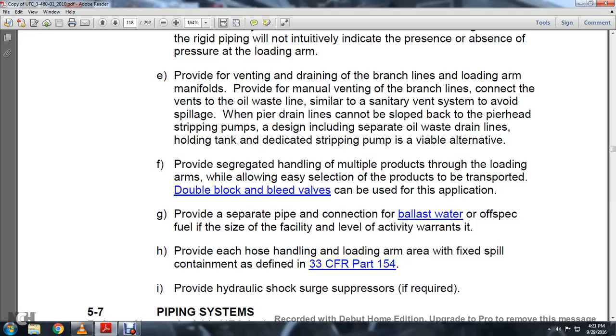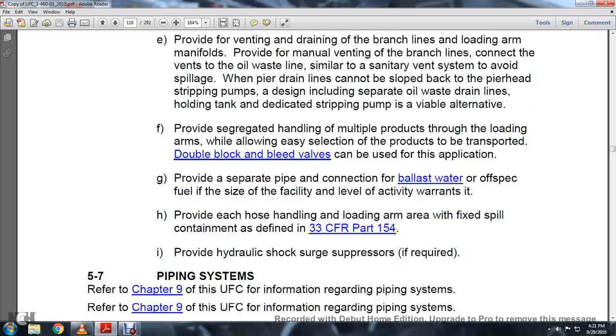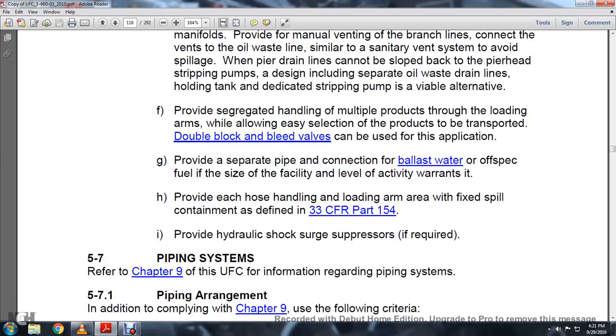Provide segregated handling of multiple products through the handling of the arms without allowing easy mixing of the products transported. Double block and bleed valves can be used for this application. Provide separate pipe and connection for the ballast water and off-specification fuels. Provide each of the hose handling and loading arm areas with fixed spill containment as defined in the statute 33 Code of Federal Regulations Part 154. Provide hydraulic shock suppressors if required.